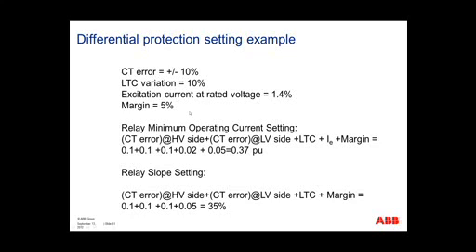So setting up our slope, we have a CT error of plus or minus 10%, a load tap changer variation of 10%, overexcitation current at rated voltage around 1.4%, and our margin of error at 5%. We add these different errors up, which gives us a minimum pickup setting of around 0.37 per unit.